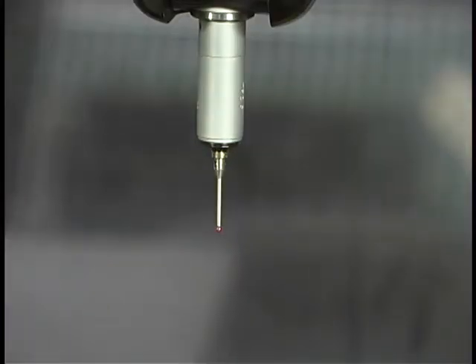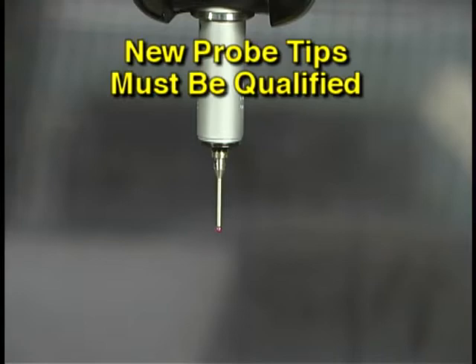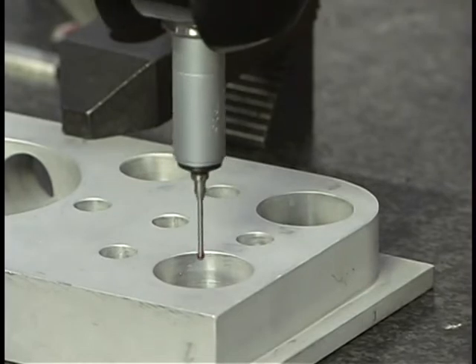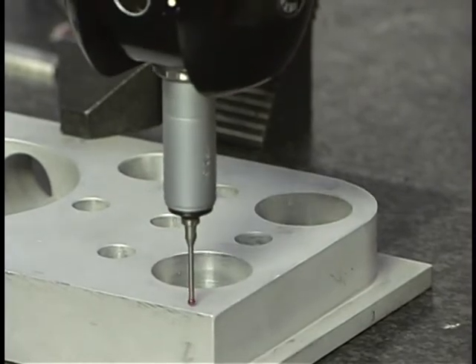Once the new probe is installed, the new tip must be qualified. Qualifying will let the computer know the diameter of the tip so that all measured values can be compensated.